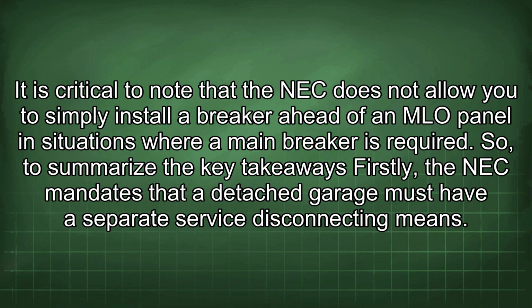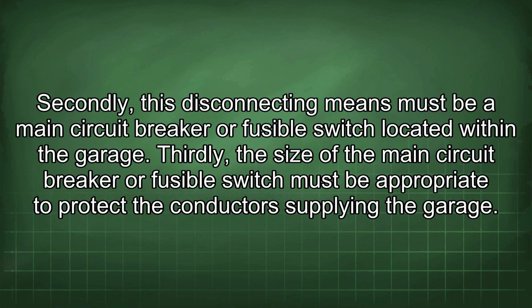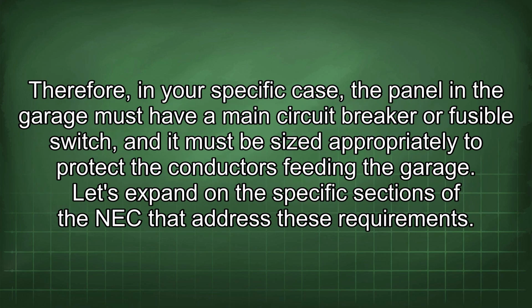So, to summarize the key takeaways: firstly, the NEC mandates that a detached garage must have a separate service disconnecting means. Secondly, this disconnecting means must be a main circuit breaker or fusible switch located within the garage. Thirdly, the size of the main circuit breaker or fusible switch must be appropriate to protect the conductors supplying the garage. Therefore, in your specific case, the panel in the garage must have a main circuit breaker or fusible switch, and it must be sized appropriately to protect the conductors feeding the garage.